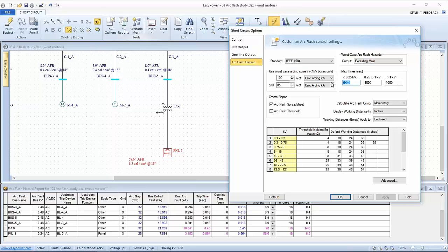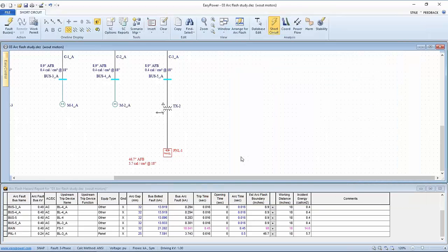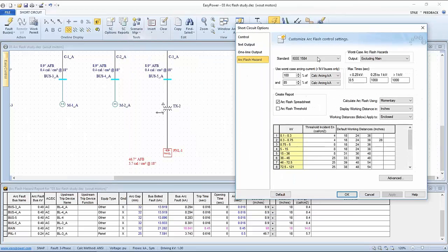If we consider half a second to give us almost 100% guard band versus the natural life of an arc at that voltage, then there's some reason to believe that would make sense. Except in this case, it's still not giving me the amount of protection I want.